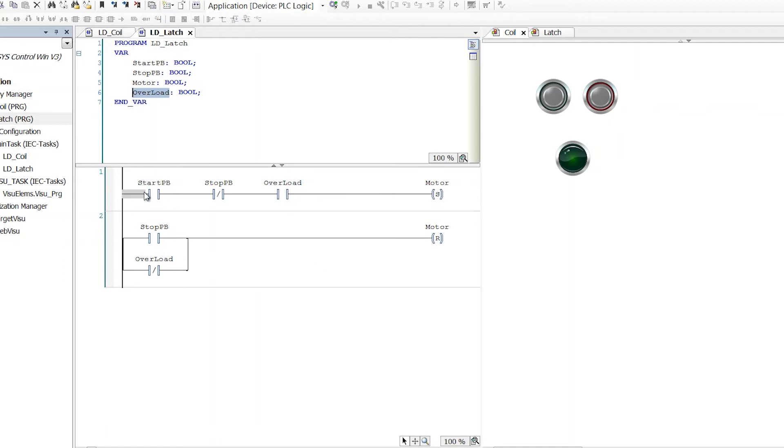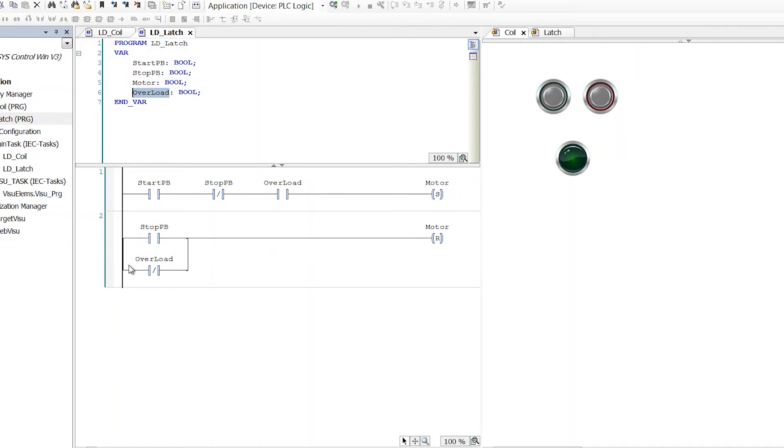So we say, if I push the start push button and I'm not pushing the stop push button and the overload is happy, it's in a permissive state, then we can run the motor. If I'm pushing the stop button or the overload is not in a permissive state, then turn the motor off.